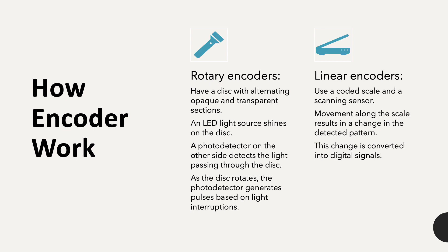The number of pulses corresponds to the angular displacement of the shaft. Linear encoders function similarly, but instead of a disc they employ coded scales with unique patterns. A scanning sensor moves along the scale and the variation in the pattern is detected and converted into digital signals representing linear movement.